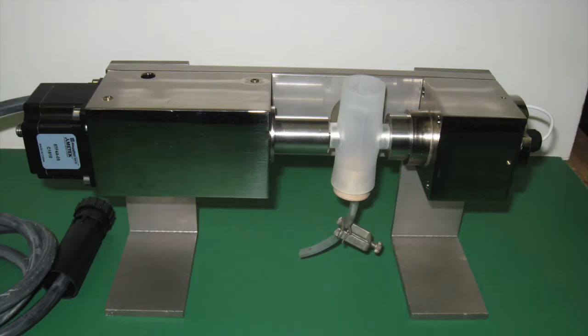The minimum sample chamber decreases sample volume to 20 milliliters for situations when only particle size is to be measured. If sample volume for particle size needs to be minimized even further, below 10 milliliters, we can use this setup. The model which uses this setup for the acoustic sensor is called the DT-1210.